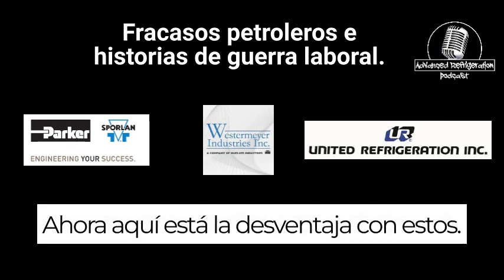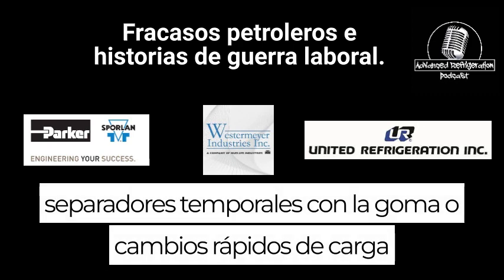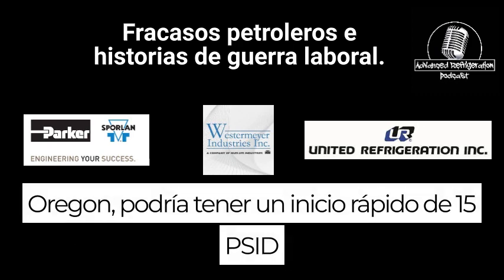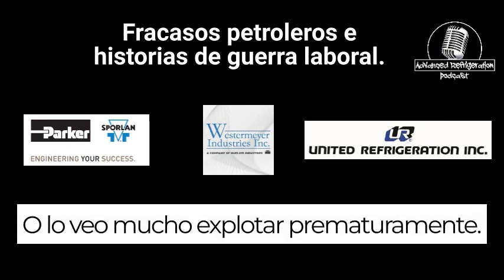Now, here's the downside with these. If you have rapid load changes, especially on the Temprite separators with the rubber O-ring, rapid load changes or on startup, you could blow that O-ring. You could have a 15 psid rapid startup pressure drop across that filter and blow that O-ring. I see it a lot, prematurely blow.